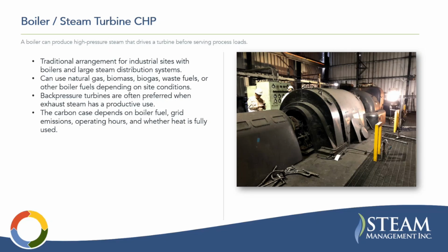Whatever the case may be, these can also often be pretty interesting, complicated configurations. But basically, you send the steam through a back pressure turbine. The exhaust of that turbine still has some pressure. So say you send a 600-pound steam into the turbine, it comes out of the back end at 100 pounds, and you have a 100-pound steam system to utilize that steam. And so that's the cogeneration there, as compared to just generating steam into a condensing turbine and trying to get all the power out of it. The carbon case here depends on the boiler fuel, grid emissions, operating hours, and whether heat is fully used.